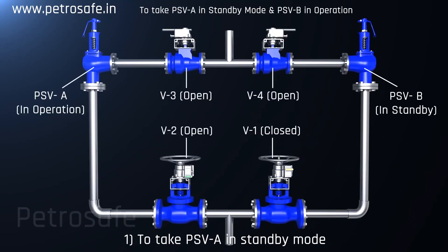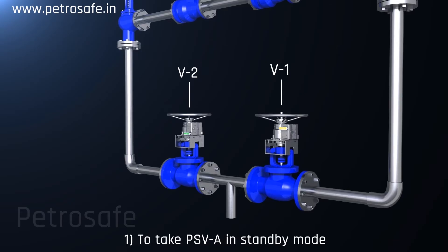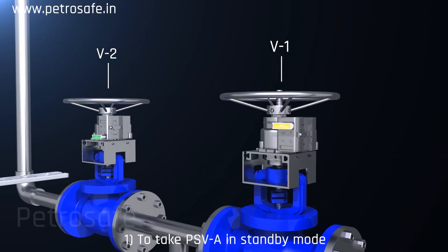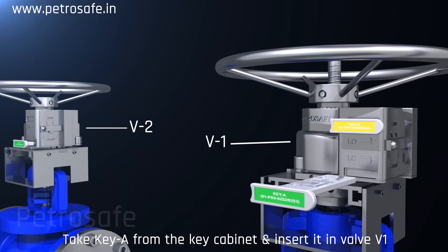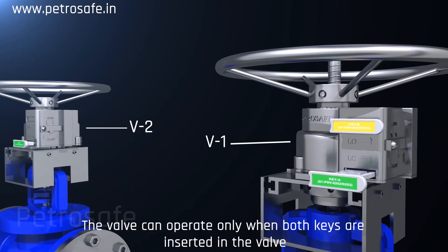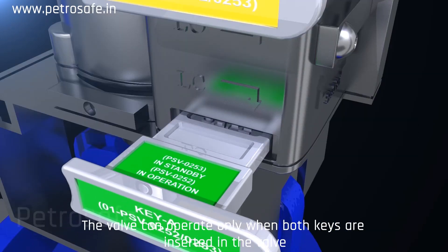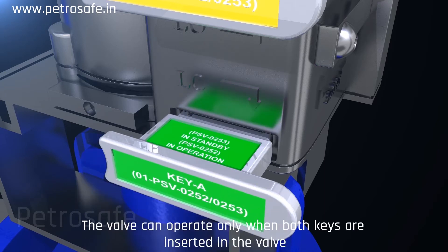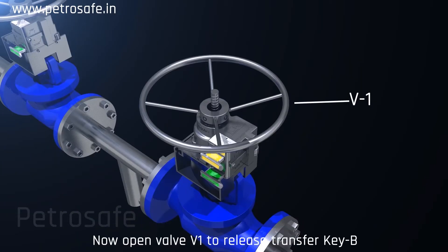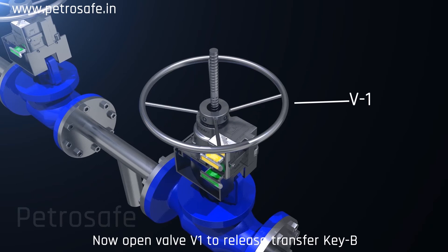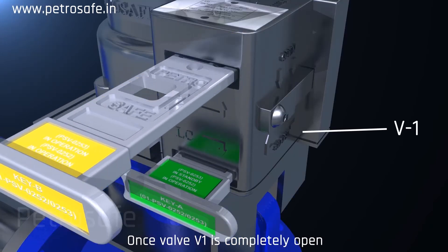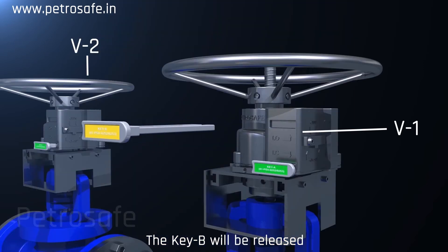Step 1: To take PSV A into standby mode. Take key A from the key cabinet and insert it into valve V1. The valve can operate only when both keys are inserted. Now open valve V1 to release transfer key B. Once valve V1 is completely open, key B will be released.